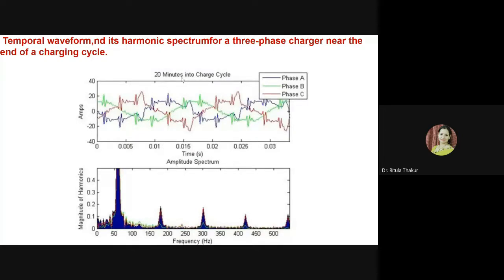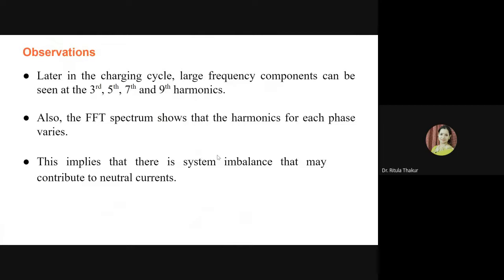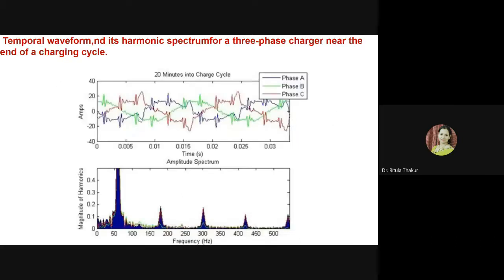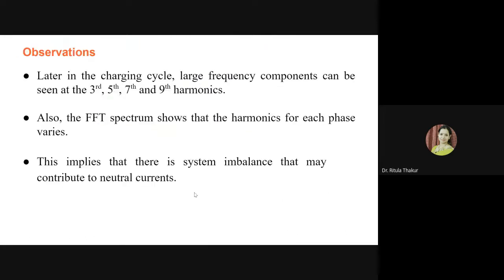However, from 20 minutes into the charge cycle, this is fast charging, so that's why we are saying approximately 20 minutes. After 20 minutes of the charge cycle, if we see the waveform and its harmonic spectrum, you can see that all three phases are nowhere near sinusoidal, they are out of phase with each other, and the other harmonics have also become very prominent as compared to the initial cycle. So what are the observations? Later in the charging cycle, large frequency components can be seen at the third, fifth, seventh, and ninth harmonics. Third is 180, fifth is 300, seventh is 420, and then there is the ninth harmonic. So they are much more prominent.